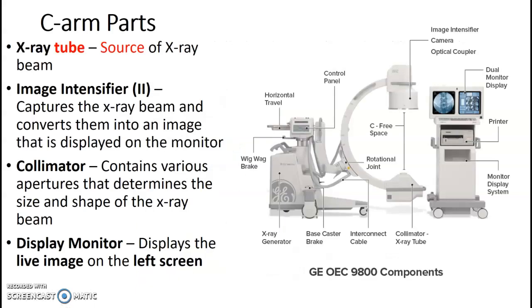So just a quick overview again of the main parts of the C-arm. The X-ray tube is the source of the beam, and that's down here. The image intensifier is up top. The beam goes through the patient and then into this image intensifier camera. This is what captures the X-ray beam, converts it to an image, and then displays it on the monitor. And most of our machines have this dual monitor as well.